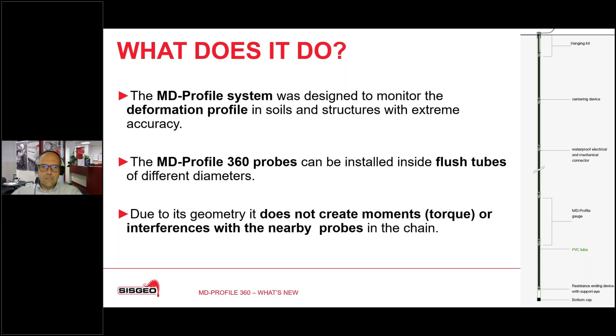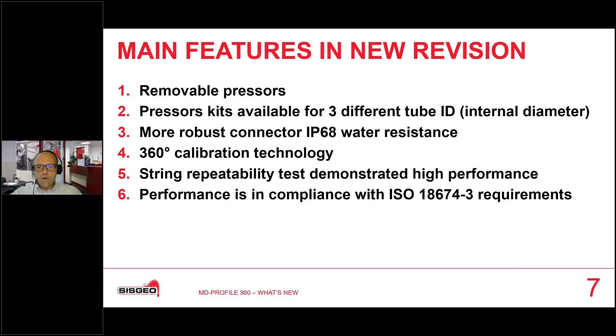This is the list of the main features in the new revision of MD Profile, MD Profile 360: removable pressors, pressor kits available for different tube IDs, a more robust connector, 360 calibration technology, string repeatability demonstrated with very deep testing, and performance in compliance with ISO 18674-3 requirements. Let's see them in detail.